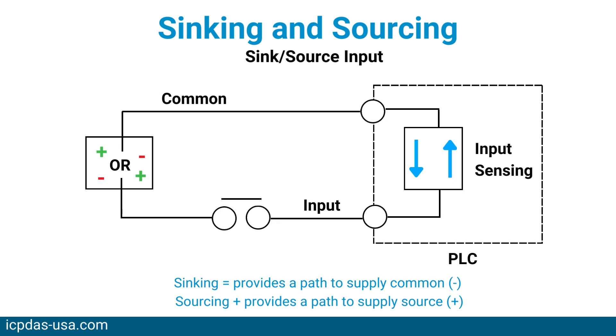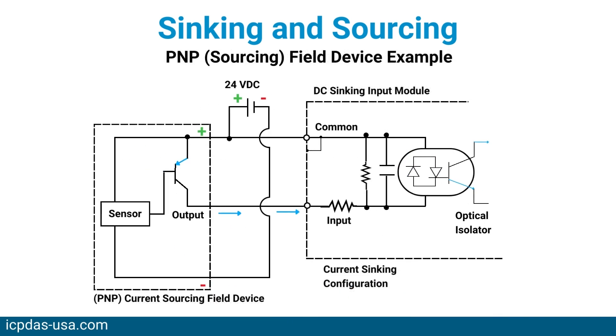These are electrical diagrams for sinking and sourcing configurations, showing typical PLC input module and field device circuitry. Note that the sinking-sourcing and sourcing-sinking pairing is always used, and never sourcing-sourcing or sinking-sinking.